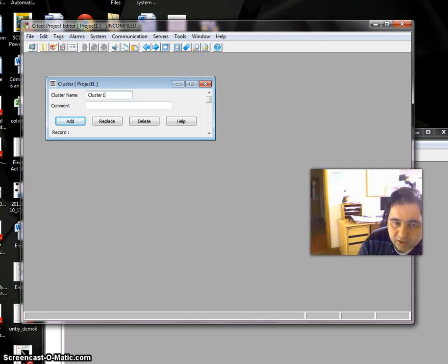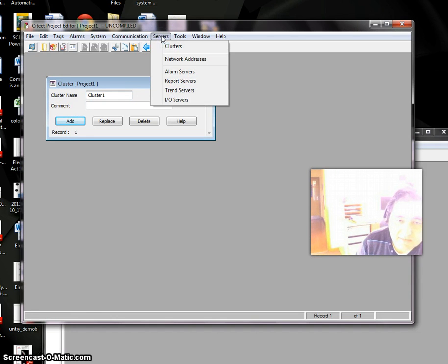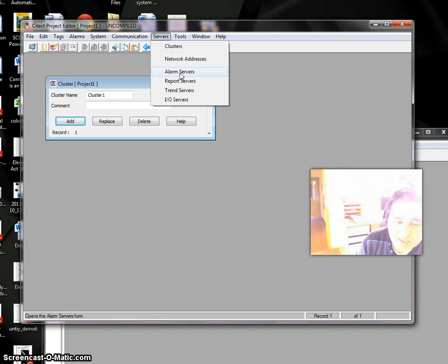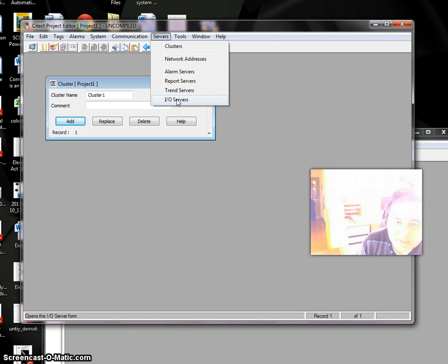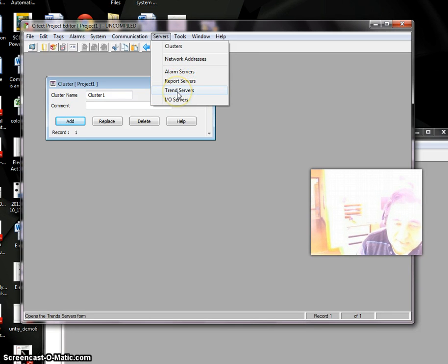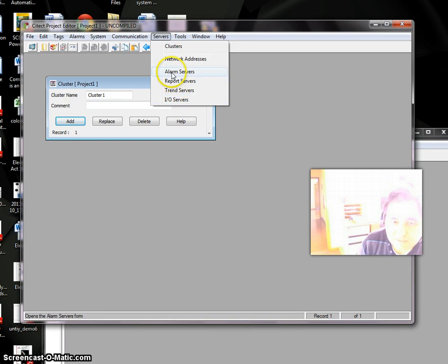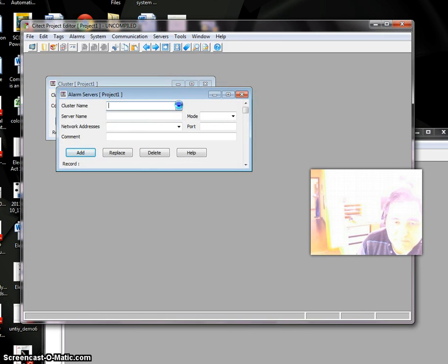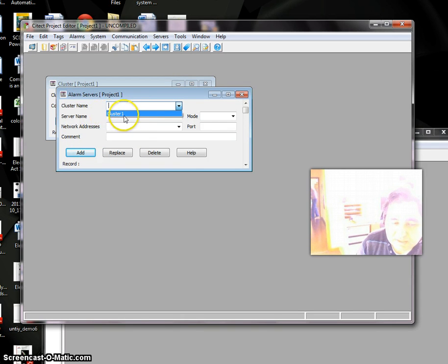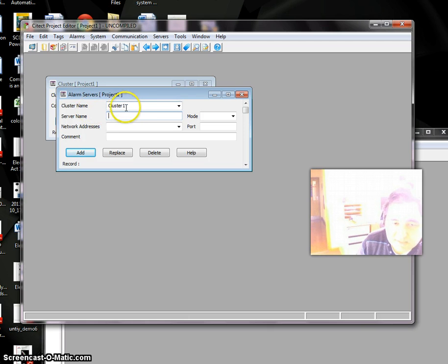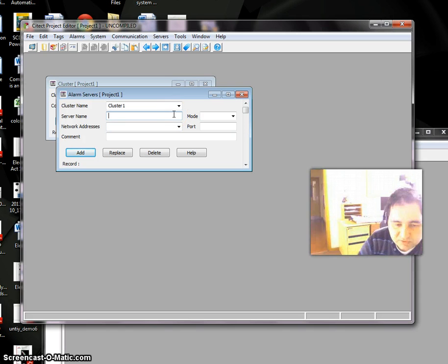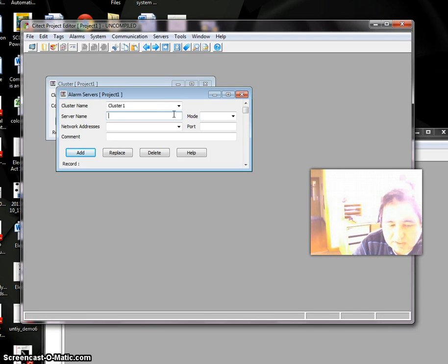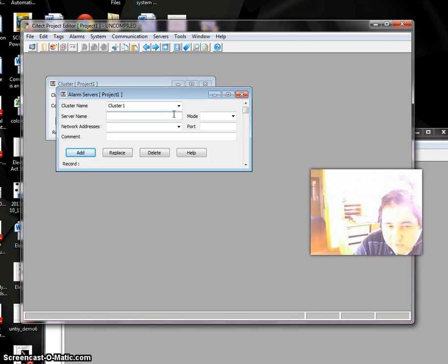The next level is describing servers. We should have one Alarm Server, one Report Server, one Trend Server, and one IO Server. We need to manually enter Alarm, Report, and Trend servers, but for IO Server we can use the wizard. For any server, I have to say which cluster will hold this server. If I have just one cluster, I don't need a network address, but with multiple clusters, network address is required.